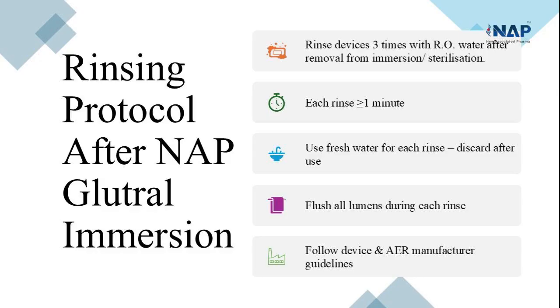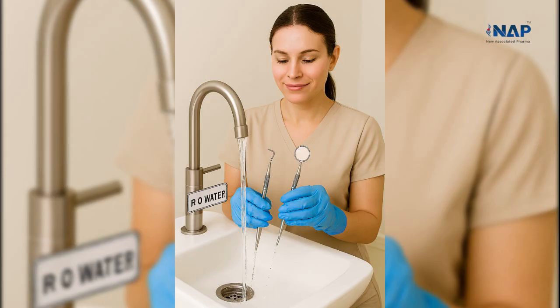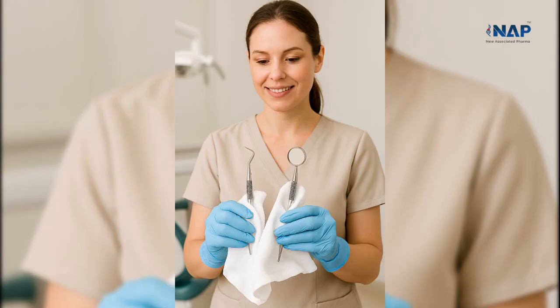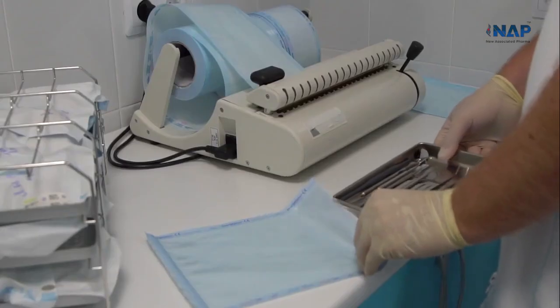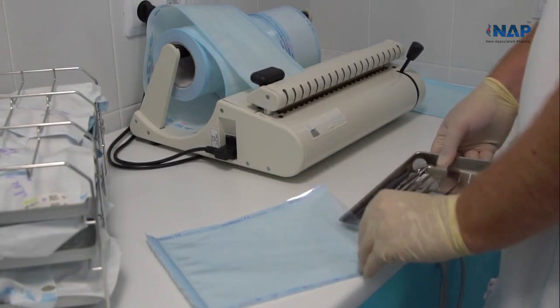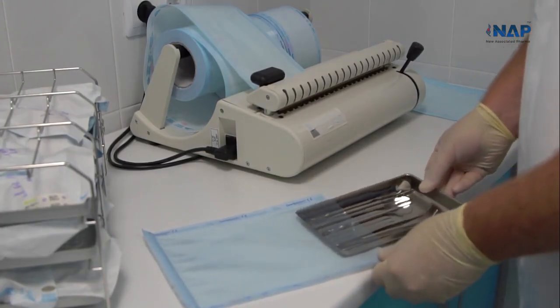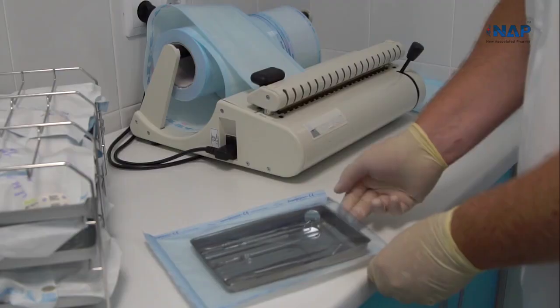After immersion, rinsing is essential. Rinse devices 3 times with RO water, ensuring each rinse lasts at least 1 minute. This step is vital to remove any residual solution and prepare the device for drying. While RO water is ideal, rinsing with potable water may pose a risk of bacterial growth. Proper drying, packing, storing are essential to prevent recontamination. Use terminal sterilization after packing for maximum protection and follow specific storage instructions to maintain device integrity.